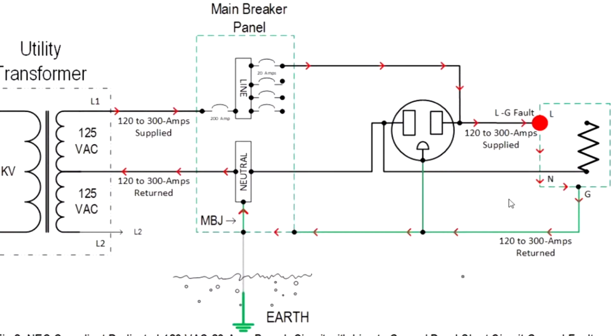Let's say we could make a 10 ohm ground, and instead of having this wire, we just have it go to Earth, and we got 10 ohms. Well, think about 120 volts with a 10 ohm circuit: that is 12 amps of current. What's 12 amps going to do to a 20 amp breaker? Nothing, right? But ground is doing something.